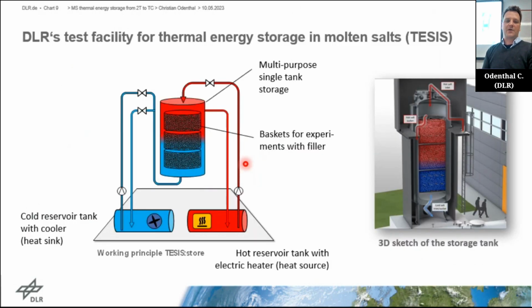And now, from our side at DLR, we have a molten salt test facility where we also look at these three single tank storage concepts. And on that picture, you can see a very basic working principle of our plant. So we have a hot reservoir tank which acts as a heat source, and we have a cold reservoir tank which acts as a heat sink, basically. And these supply hot and cold salt to our single tank thermal energy storage. And for maintaining the temperature levels, you need an additional electric heater in the hot reservoir tank, and also a cooler in the cold reservoir tank. So if hot salt flows into the cold tank, you need to cool it down, and vice versa on the hot tank. So that is the working principle.